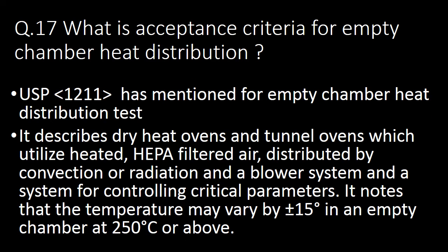Next question: what is the acceptance criteria for empty chamber heat distribution? USP Chapter 1211 has mentioned requirements for empty chamber heat distribution test. It describes dry heat ovens and tunnel ovens which utilize heated HEPA filtered air distributed by convection or radiation and blower system, with a system for controlling critical parameters. It notes that temperature may vary by 15 degrees Celsius in an empty chamber at 250 degrees Celsius or above.